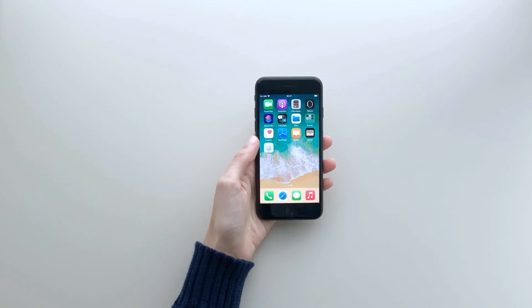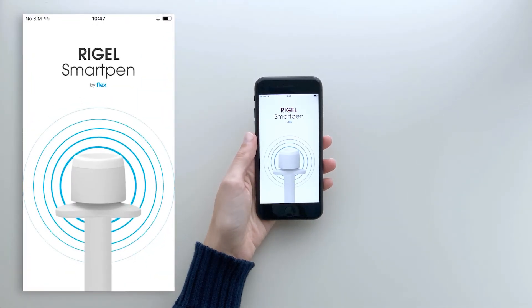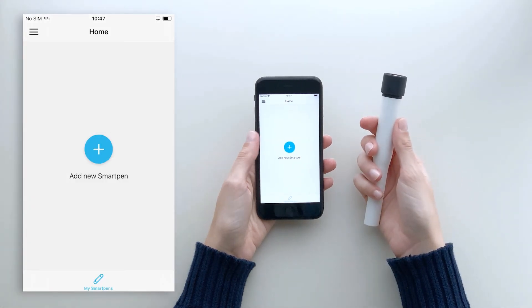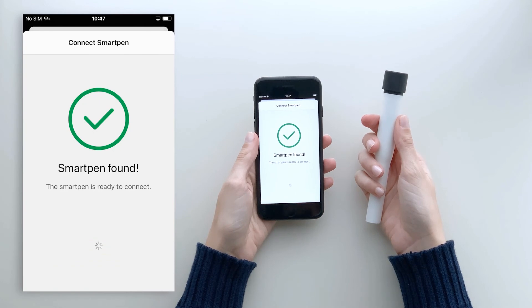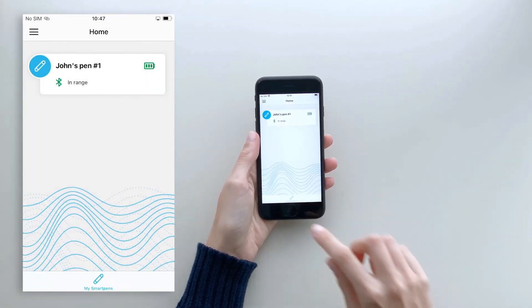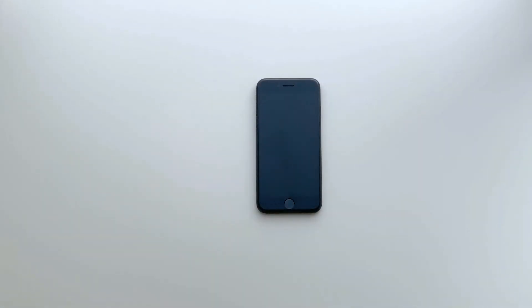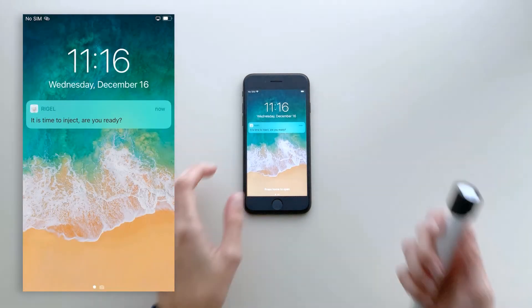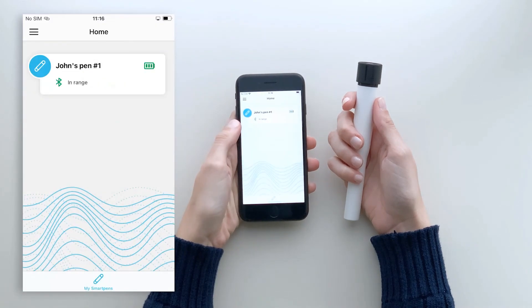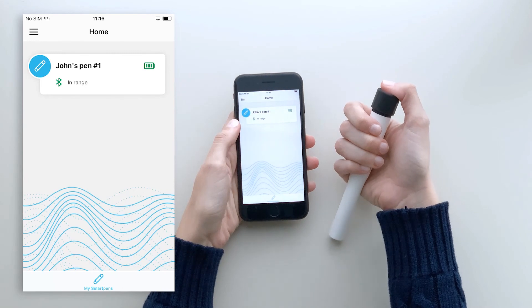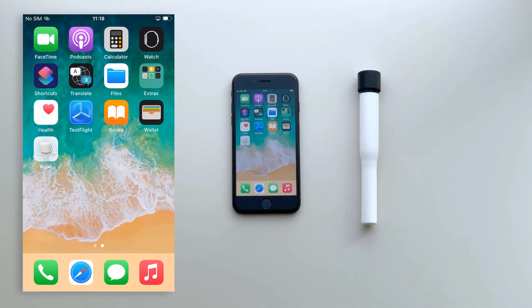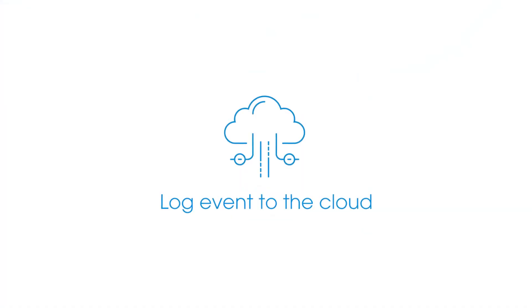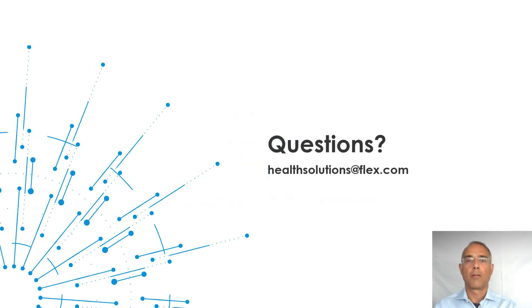With the BLE solution, the first activity the user must do is set up the device. Even if it is a disposable solution, you always need to pair the BLE device with a smartphone — this can be done via QR codes or NFC tags. Once the pen is connected to the app, you can use the app to turn on specific notifications and set up reminders at the right point in time, enabling better adherence to the prescribed injection schedule. When the user is ready to inject and activates the button, the injection event is transferred to the app, stored in local smartphone memory, and can later be transferred to the cloud for further logging.